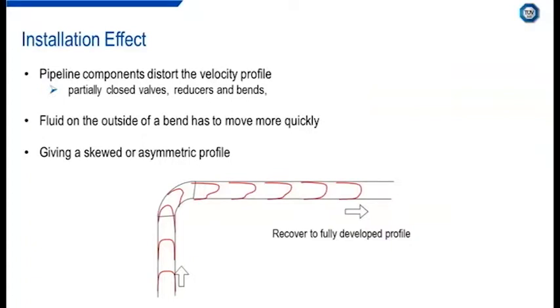An important consideration for flow metering and the selection of a suitable flow metering technology is installation effects. The impact that installation effects could have on the performance of a flow meter and the flow metering technology varies depending on the particular technology selected. Valves, bends and reducers disturb the flow and the velocity profile of the fluid, resulting in a skewed or asymmetric profile, which will take a length of straight piping to recover fully back to a fully developed flow profile downstream.